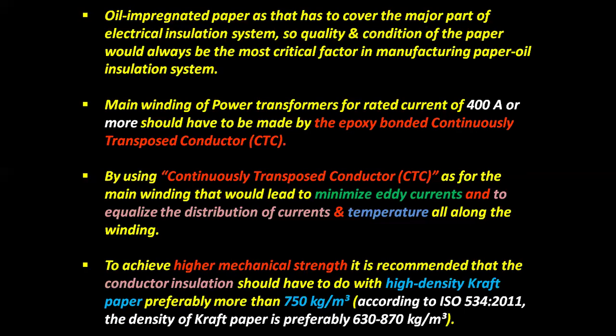Regarding the transposed conductor, CTC, we have already discussed it in a previous article. Using continuously transposed conductor, CTC, for the main winding leads to minimized eddy currents and equalized distribution of currents and temperature all along the winding.